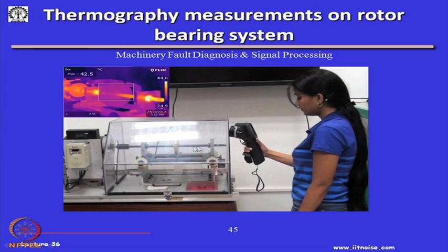And this is what I was telling you regarding the infrared image in our laboratory, wherein my student is holding this FLIR camera, and you have the bearings. This is the coupling. So the rate of temperature rise, we can artificially introduce misalignment in this system. This is the coupling, this is the drive end bearing, this is the non-drive end bearing, this is a motor behind it, and this is a flexible element coupling. So through IR imaging, you can see the temperature rise.